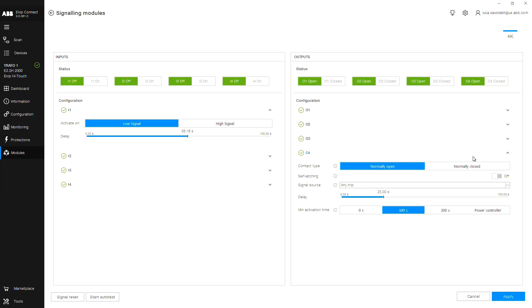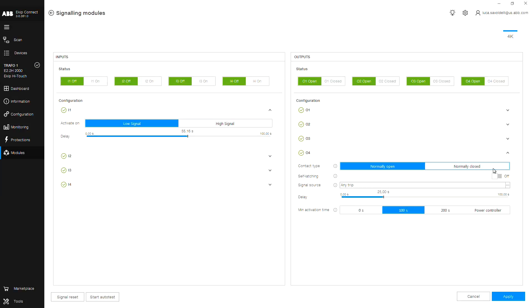Choose the contact type between normally open or normally closed. And also, you are able to select whether the contact is to be self-latching, meaning the output is active and the contact will remain closed or open until it is manually reset via the signaling reset input.